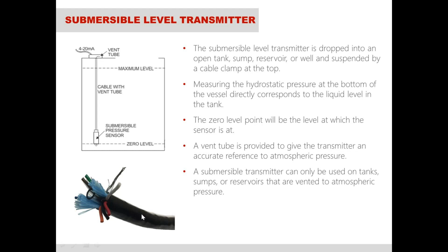of the tank. And the way we do that is we have a vent tube that goes all the way from the sensor here up the cable and then out into the atmosphere. And you can see here's a picture of our cable. You can see all the wires coming out of it, as well as the actual vent tube here in the middle. These little blue strings here are just basically filler to give the cable some strength and structure. But this tube is what references it to atmospheric pressure.